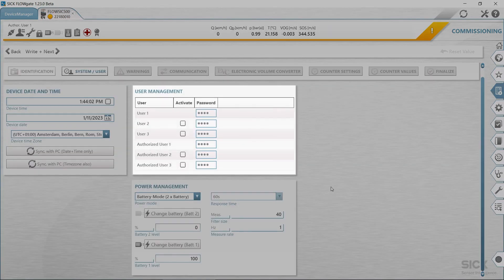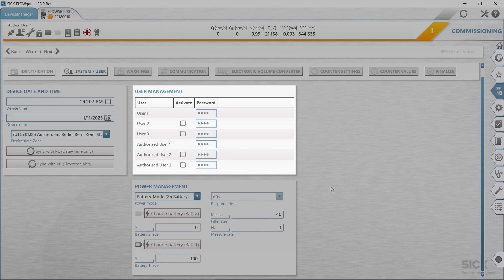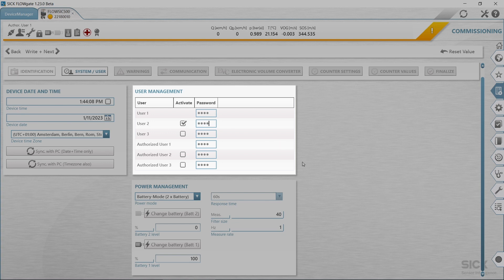For the user management, SICK recommends changing the initial password provided for the authorized user for security reasons. Further users can be activated if desired. Activate the associated checkbox of the desired user. Specify a password. The password must include four digits. Up to three users and three authorized users can be activated. Authorized user 1 and user 1 are always activated.